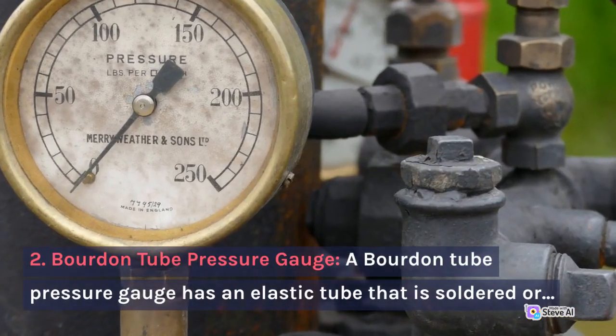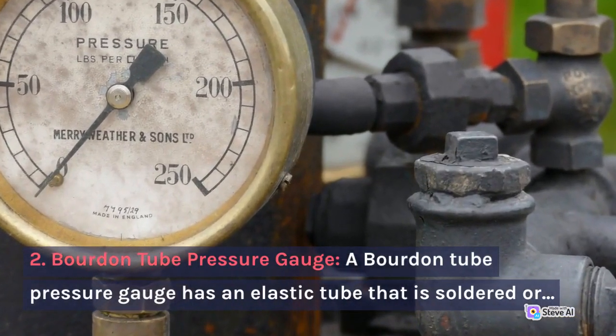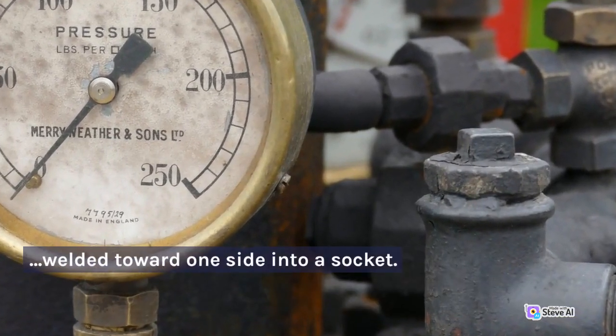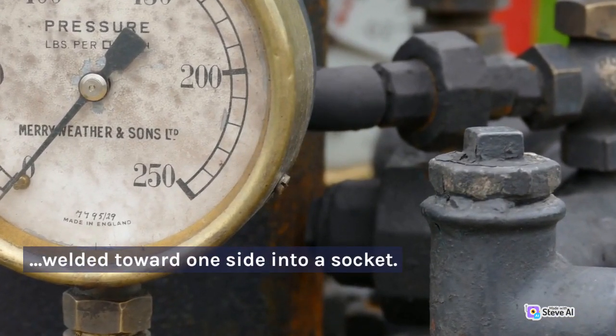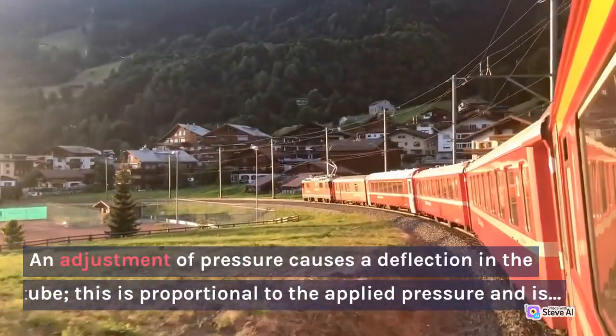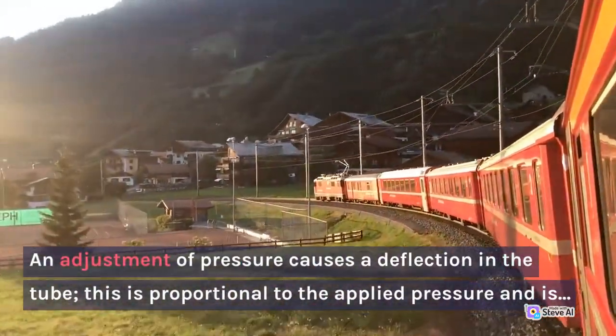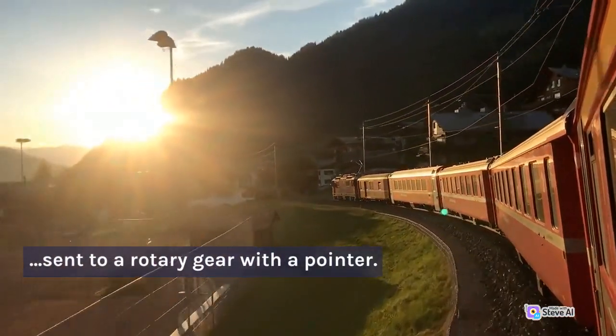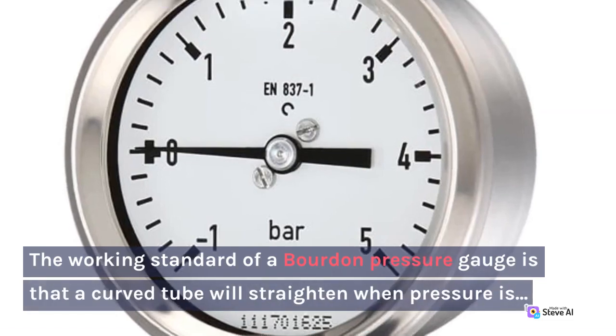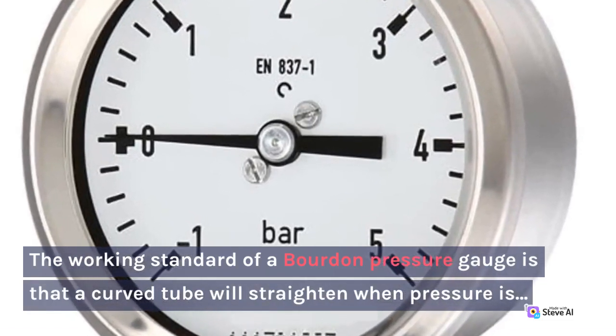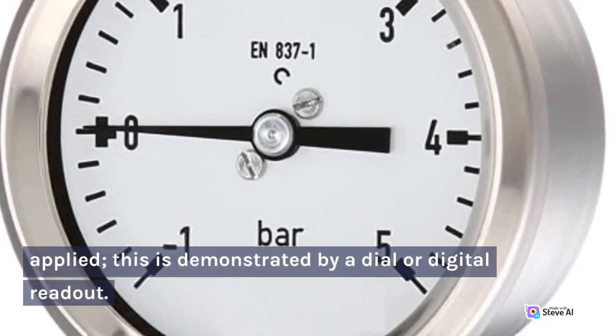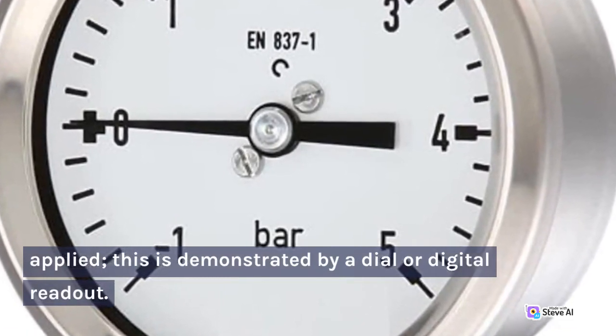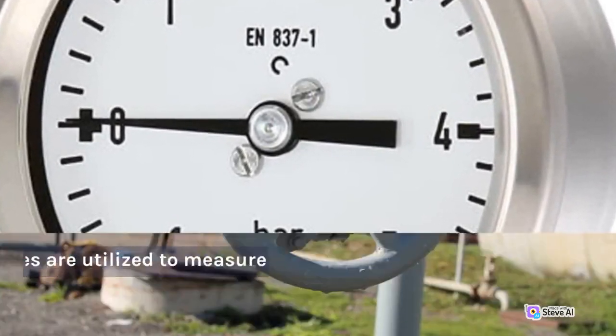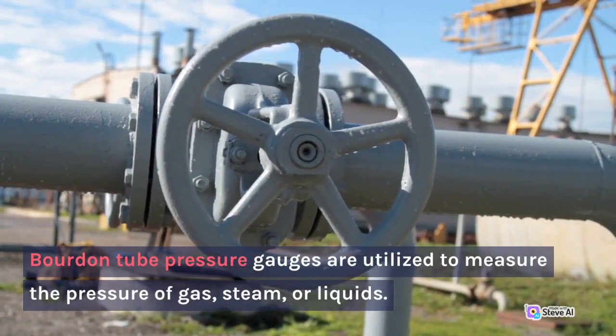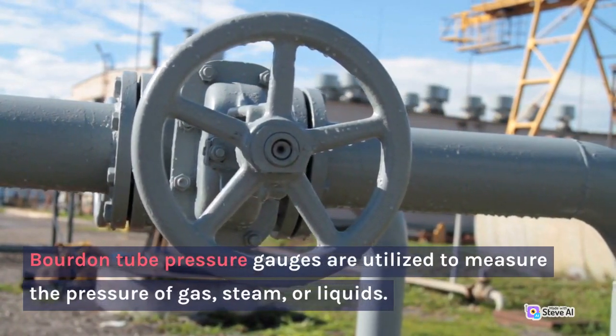2. Bourdon tube pressure gauge. A Bourdon tube pressure gauge has an elastic tube that is soldered or welded toward one side into a socket. An adjustment of pressure causes a deflection in the tube. This is proportional to the applied pressure and is sent to a rotary gear with a pointer. The working standard of a Bourdon tube pressure gauge is that a curved tube will straighten when pressure is applied. This is demonstrated by a dial or digital readout. Bourdon tube pressure gauges are utilized to measure the pressure of gas, steam, or liquids.